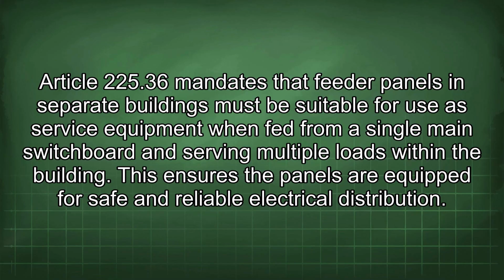Article 225.36 mandates that feeder panels in separate buildings must be suitable for use as service equipment when fed from a single main switchboard and serving multiple loads within the building. This ensures the panels are equipped for safe and reliable electrical distribution.